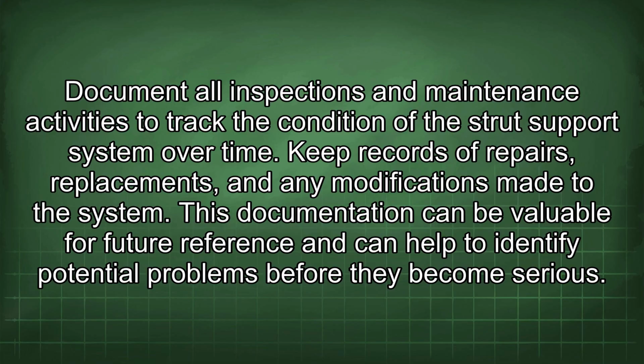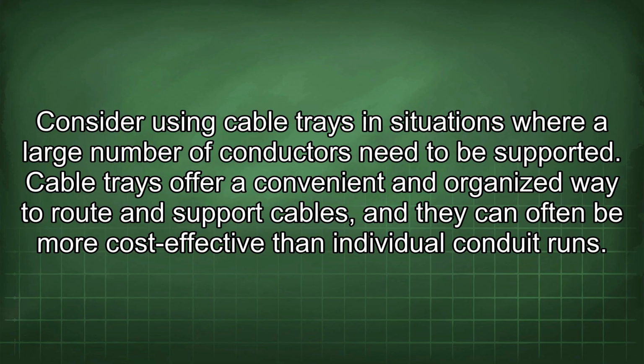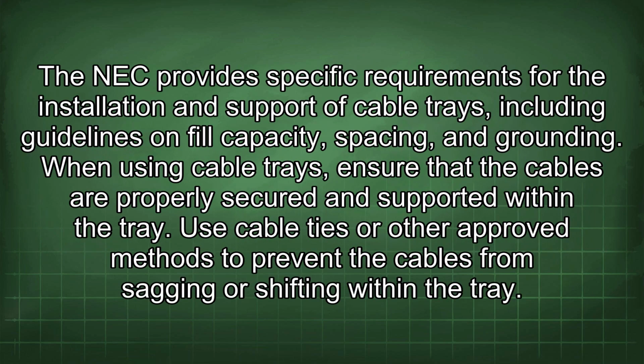Keep records of repairs, replacements, and any modifications made to the system. This documentation can be valuable for future reference and can help to identify potential problems before they become serious. Consider using cable trays in situations where a large number of conductors need to be supported. Cable trays offer a convenient and organized way to route and support cables, and they can often be more cost-effective than individual conduit runs. The NEC provides specific requirements for the installation and support of cable trays, including guidelines on fill capacity, spacing, and grounding.